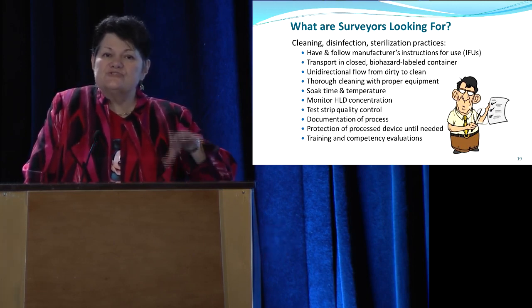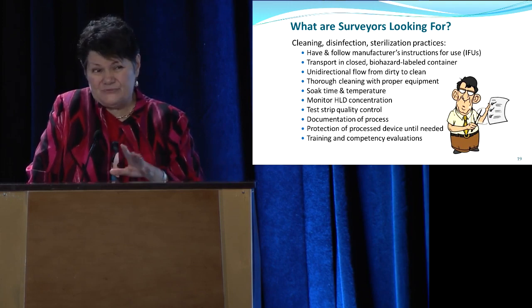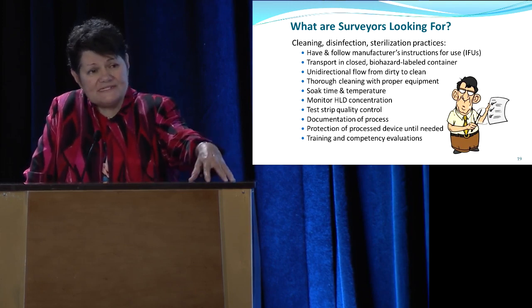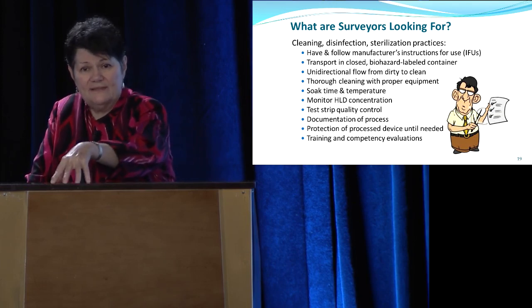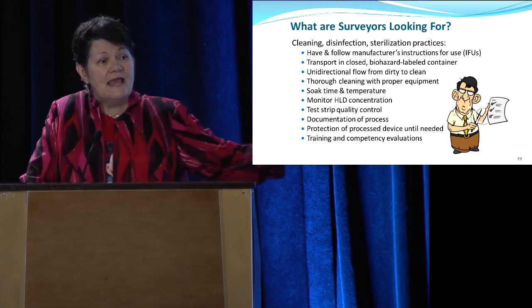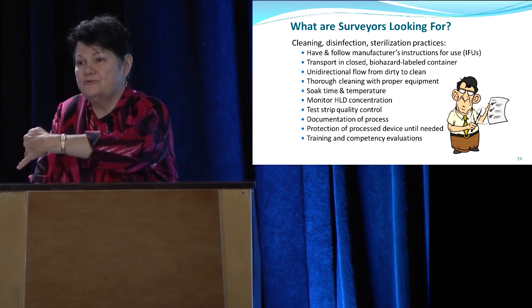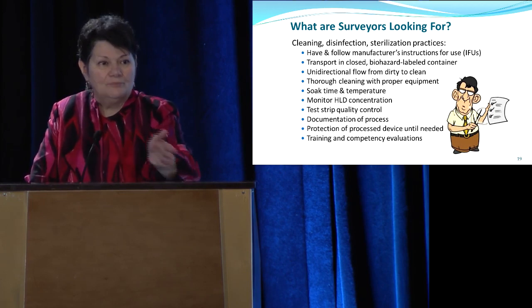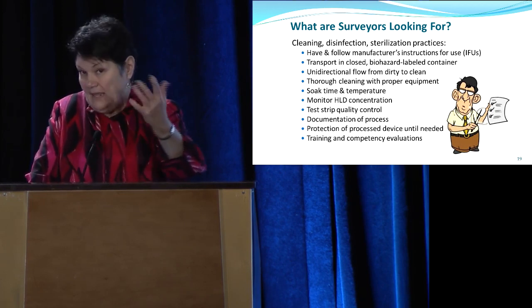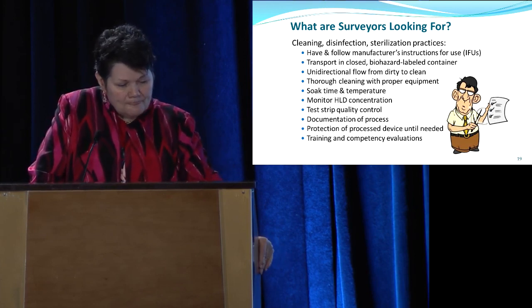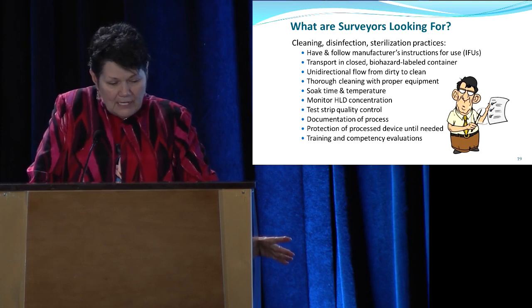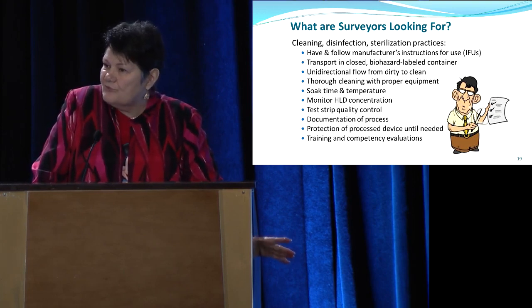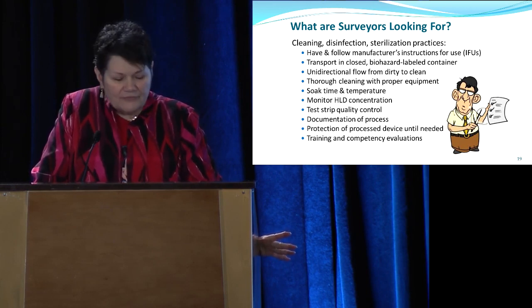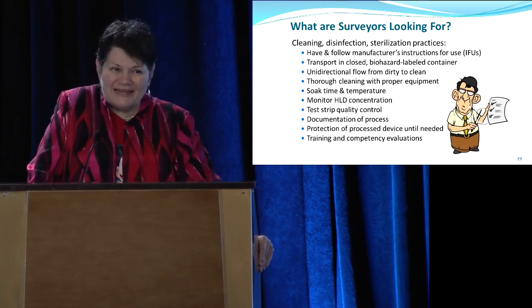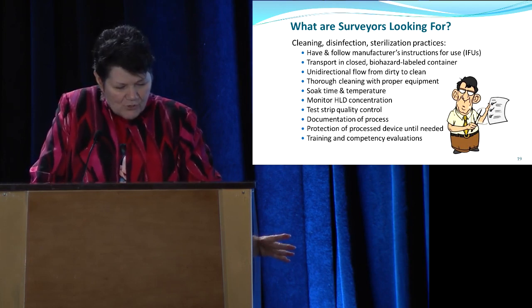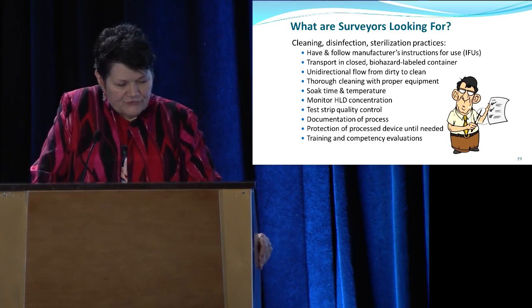You want in your soiled or clean or hopefully not combined utility room to be from soiled receiving through washing, through drying, through high-level disinfection with no crossovers, and the flow going from dirty to clean all in one direction, so nothing gets put in the wrong place and misses a step. And I've seen that happen more times than I care to count. Thorough cleaning with the proper equipment. You guys don't usually have to deal with brushes and lumens and things like that. That's a wonderful thing. But you need to be sure that you're getting all the gel and secretions off the probes, regardless of what they're used for.